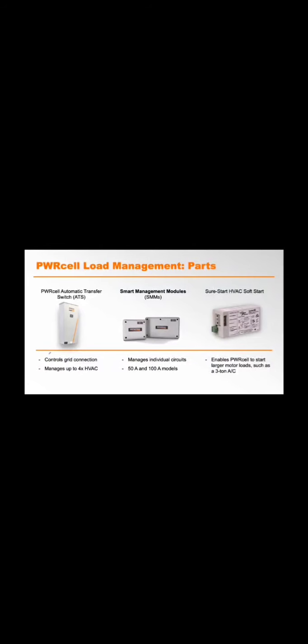Smart management modules do most of the actual load management. They install in line to existing home wiring. You can install up to 8 of them. When the inverter is having a hard time meeting the demand of transferred loads, it sends a signal to the SMMs, which drop the loads in reverse order of priority, so that the most essential loads are never interrupted. Lastly, we have the SureStart HVAC accessory right here. Basically, you connect this to an HVAC unit, and it drastically reduces the locked rotor amps, or startup surge, on AC units, meaning that starting a 3-ton AC, even when there is base load in the home, is no trouble for even a single PWRcell battery. So these are some of the components of a higher performance load management system.